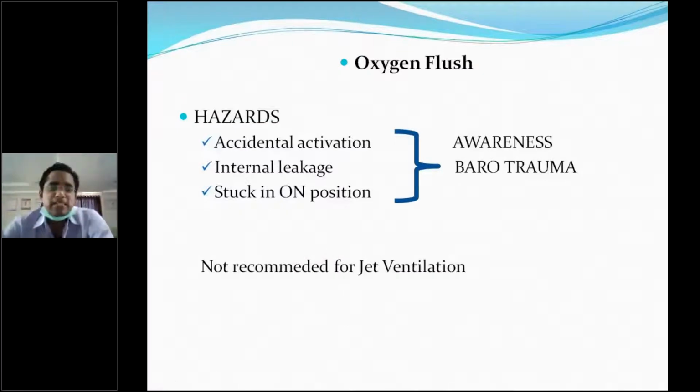Again, you have a few hazards for oxygen flush. One is awareness. What is awareness? When you press this oxygen flush, there will be more oxygen going, and there will be dilution of the anesthetic gases. When there is reduction in the anesthetic gas, the patient will come out of anesthesia, and the patient will have awareness.